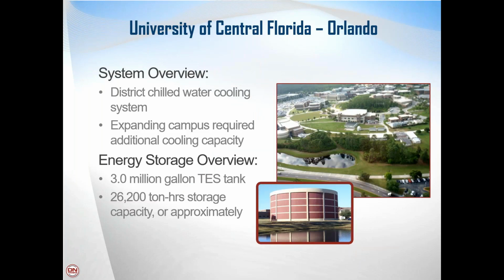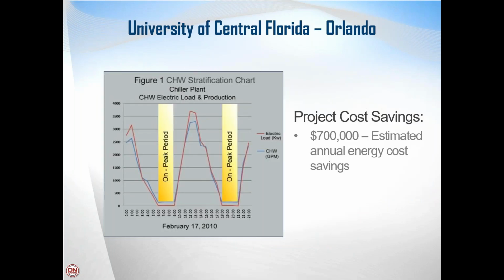Very similarly, this is a college campus in Florida. They were looking at expanding their campus. They also chose to add a thermal storage tank. This was a 3 million gallon thermal storage tank instead of adding more chillers. But the reason I like to show this example is that in Florida, in the wintertime, they actually have 2 peak periods of time that they are trying to avoid energy use. There's a morning peak period of time, which you can see here is between 7 and 9 in the morning, and an afternoon peak period of time.